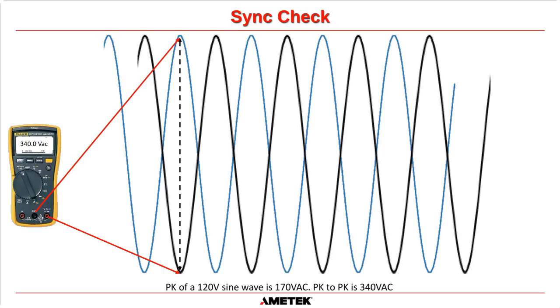If you had a completely out of phase system, which you can see in this waveform here, the lowest peak of the bypass compared to the highest peak of the inverter is the full peak-to-peak voltage. For this example, it's a 120 volt sine wave, so the peak voltage is 170 volts and peak to peak is 340 volts. So you can measure up to 340 volts for a sine wave that is exactly 180 degrees out of phase. There is 340 volts when it gets to the peak of that, that voltage potential between the two.